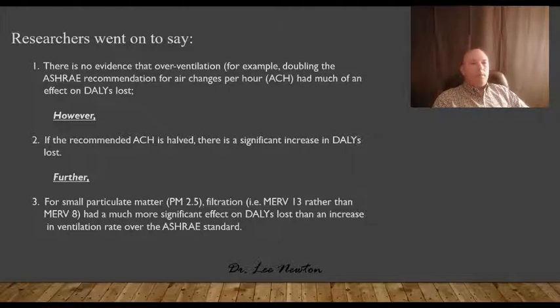If you doubled the rate of ventilation above the ASHRAE recommendation for your facility, there wasn't much of an effect on DALYs. Your health isn't going to go up very much. But if you cut it in half, there's a significant increase in DALYs lost. So my suggestion would be obey the ASHRAE standard, you'll be fine.